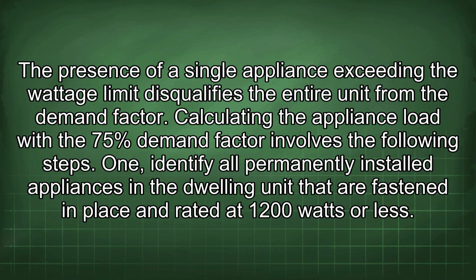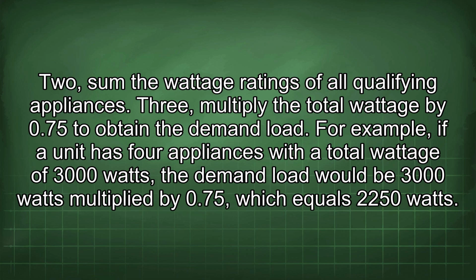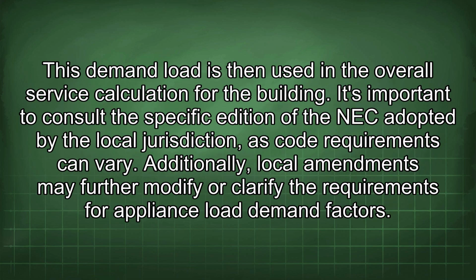Calculating the appliance load with a 75% demand factor involves the following steps. 1. Identify all permanently installed appliances in the dwelling unit that are fastened in place and rated at 1200 watts or less. 2. Sum the wattage ratings of all qualifying appliances. 3. Multiply the total wattage by 0.75 to obtain the demand load. For example, if a unit has 4 appliances with a total wattage of 3000 watts, the demand load would be 3000 watts multiplied by 0.75, which equals 2250 watts. This demand load is then used in the overall service calculation for the building.